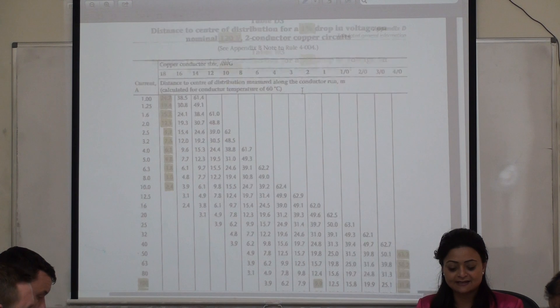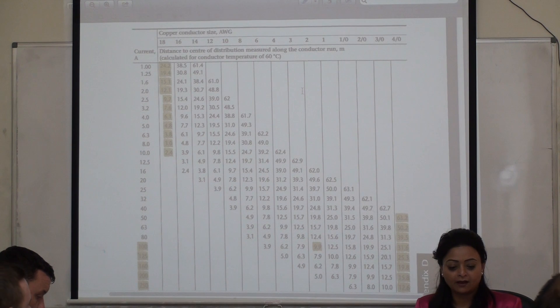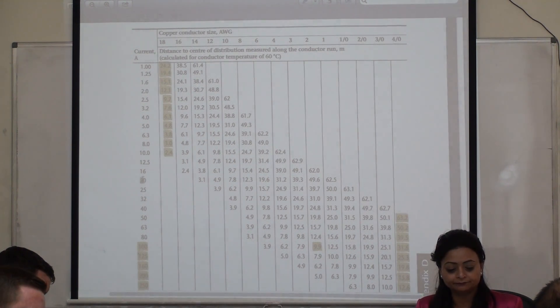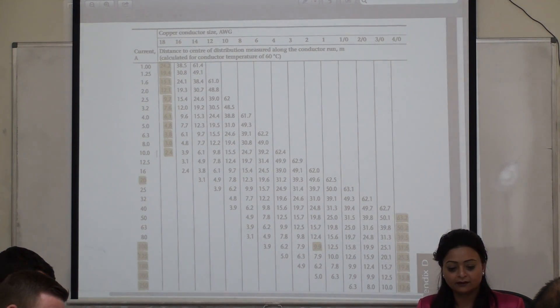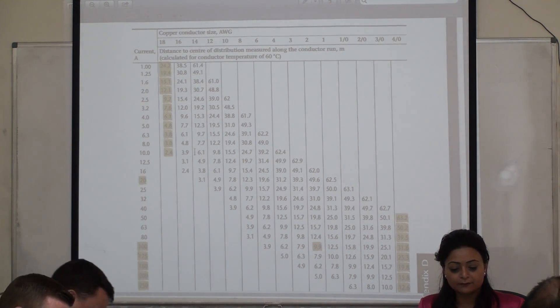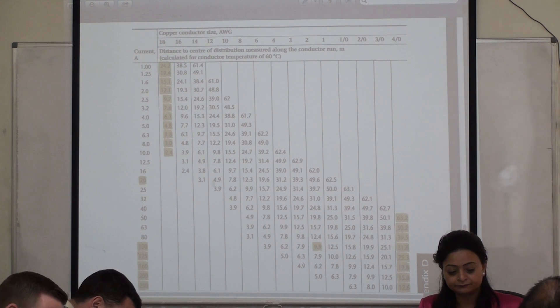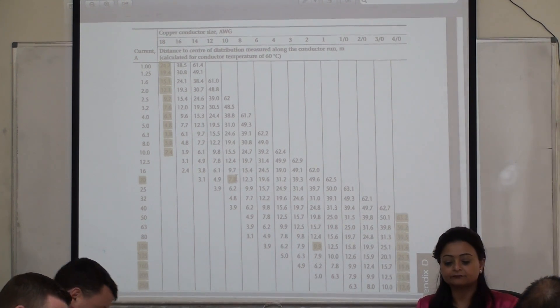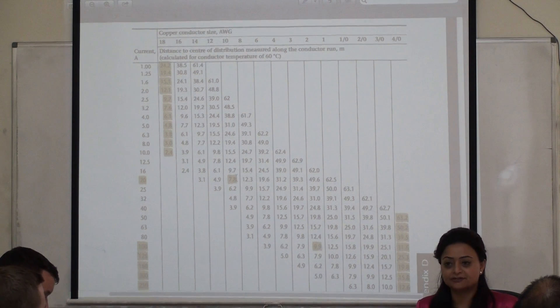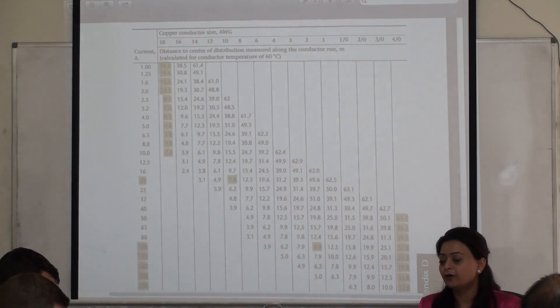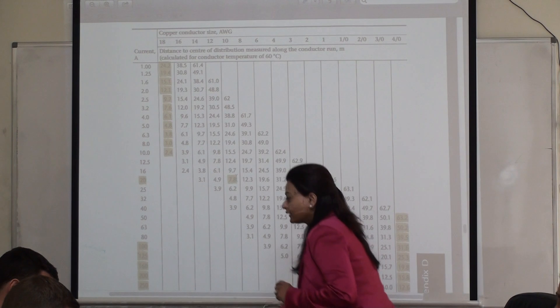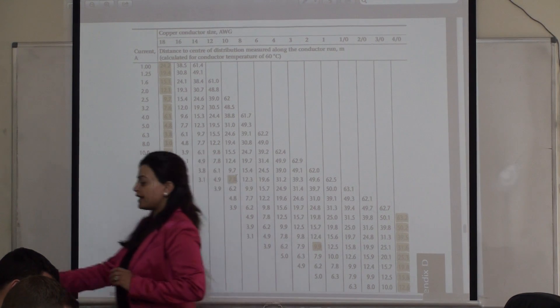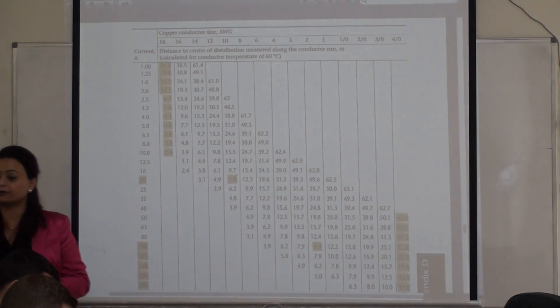Take another example: I have a 20-amp load and I'm using Number 10 wire. How far can this conductor go? 7.8 meters, and that's it. Your two points of coordinate are given and you're finding the third point of coordinate.